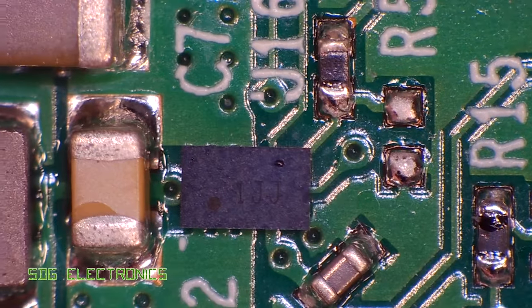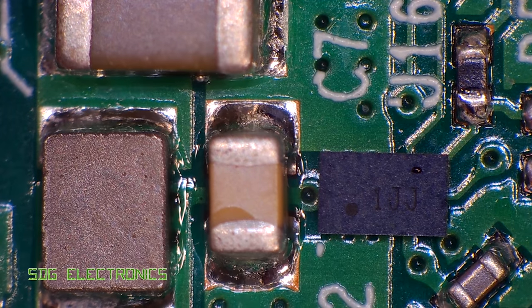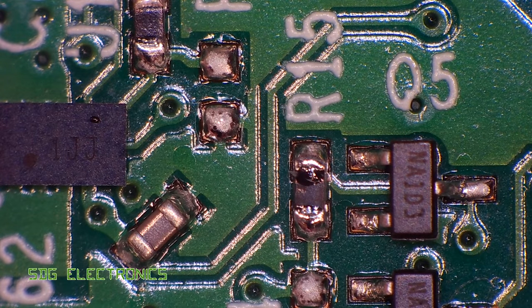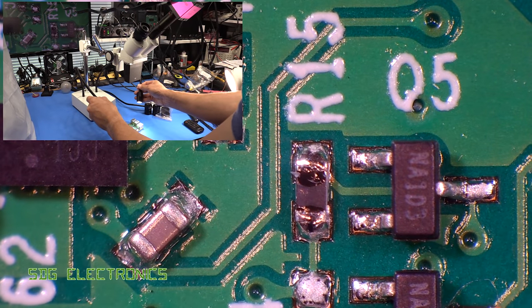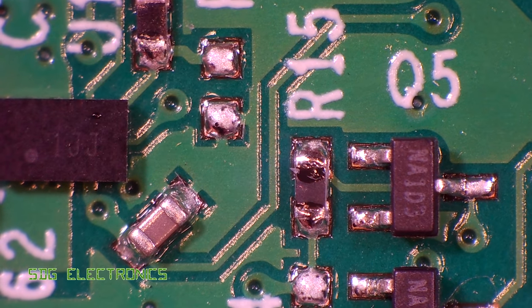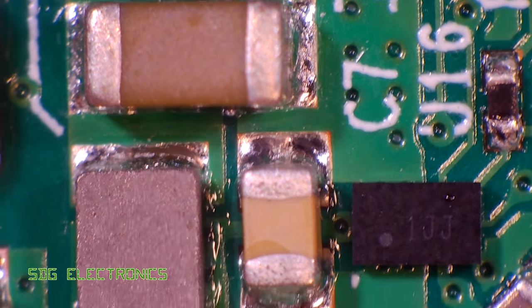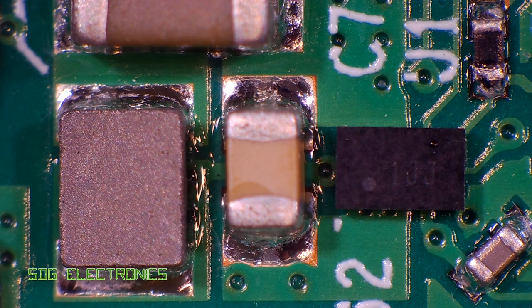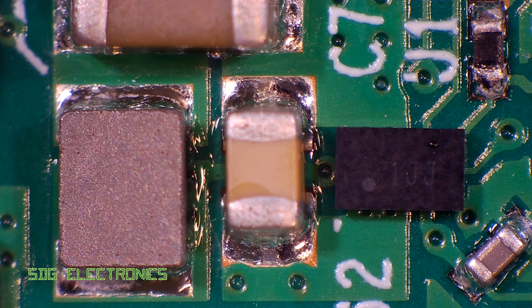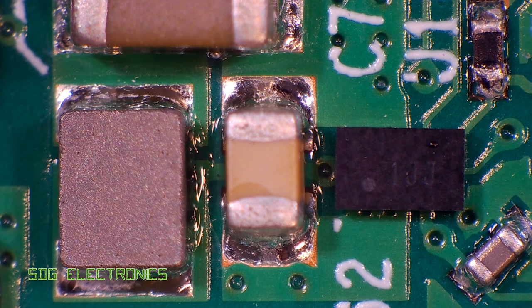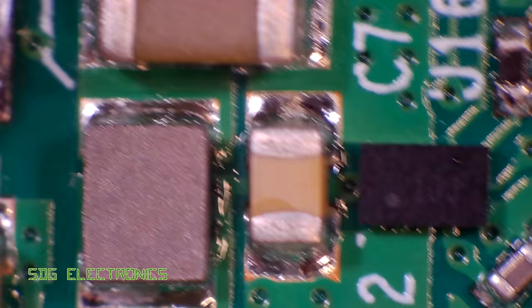As I said, through the eyepieces the image quality is actually really good, and the gooseneck lights provide a lot of versatility for providing good lighting. So at the moment we've got it up near the objective lens, but if we give it a little bit of a wider vision you can see we can really change the effect of the 3D vision through the microscope. So you've got a lot of scope for adjustment rather than using a ring light, because if there's any reflections or anything like that which you often get with ring lights, you can move the gooseneck light slightly and then you can see the image perfectly clear.